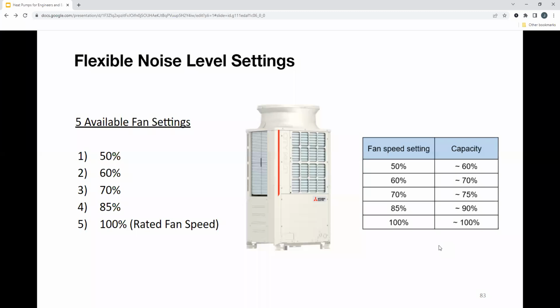Flexible noise level settings. This isn't necessarily an energy save mode, but this is a question that I also get asked a lot. This has to do with fan speed settings and dip switches that you can hit on the outdoor unit itself. But in the case where you live in Cambridge, or you're doing a project in Cambridge or other places that have sound ordinances, you need to be below a certain decibel rating at a certain time period throughout the night. You have your condenser ratings.